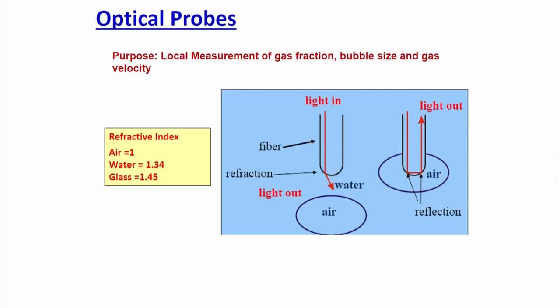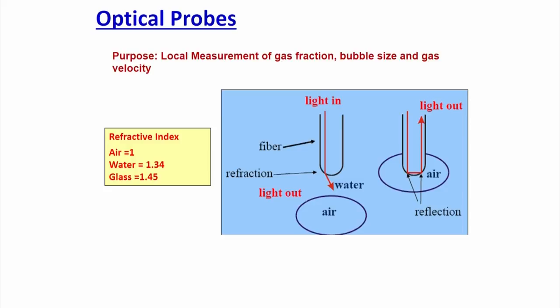Next is the optical fiber probe, which overcomes several HWA limitations. With the development of optical fiber probes, researchers applied this technique to multi-phase flow velocity measurement. In an optical fiber probe casing, there are two wires: one emits light and another receives or absorbs light. Each phase has a different refractive index — for example, in air-water systems, air has refractive index 1 and water 1.34 — so the reflected light intensity differs for each phase.